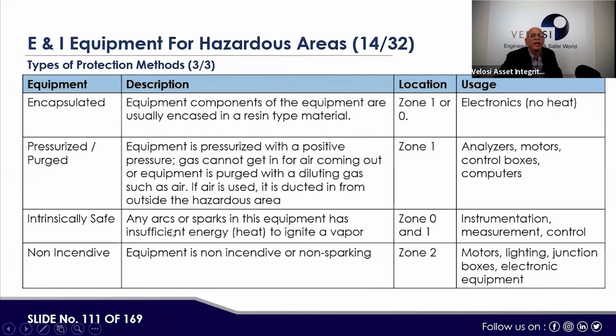Intrinsically safe means any arc or spark in that equipment has insufficient energy and will not act as an ignition source in that particular zone. It is normally applicable to instrumentation, even mobiles and others. Then non-incendive: the equipment is non-incendive or non-sparking, meaning motors, lighting, junction boxes, and electric equipment. This is for zone 2.